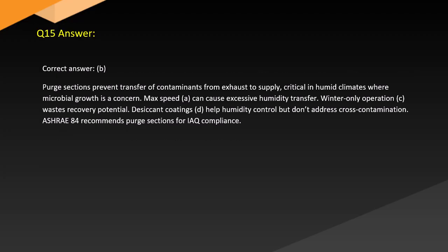Answer. Correct answer: B. Purge sections prevent transfer of contaminants from exhaust to supply, critical in humid climates where microbial growth is a concern. Max speed, A, can cause excessive humidity transfer. Winter-only operation, C, wastes recovery potential. Desiccant coatings, D, help humidity control but don't address cross-contamination. ASHRAE 84 recommends purge sections for IAQ compliance.